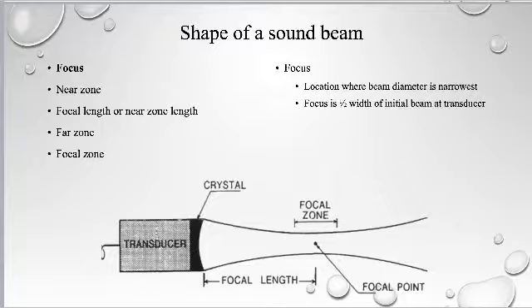Okay, just like your transducer essentially has a Fresnel lens, and it lenses the sound into a focal point by interference patterns. So it lenses the sound down because of interference patterns, and that's what's happening with the light in these little lenses. It's causing interference patterns, which in this case magnify the light, and in our transducer, the interference patterns cause it to focus down. So if you have trouble reading, you can use one of these to put on your paper and read a little better. Yeah, they work. They really do, and they're flat, they really are.